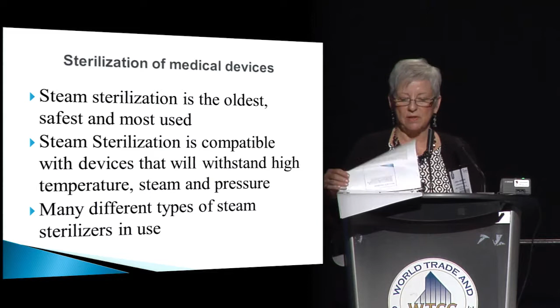Steam sterilization by gravity is the oldest method used. Steam enters the chamber from the top, moving the air towards the drain vent at the bottom of the chamber, causing the displacement of air. It's very important that all the air is removed from the chamber and packages.